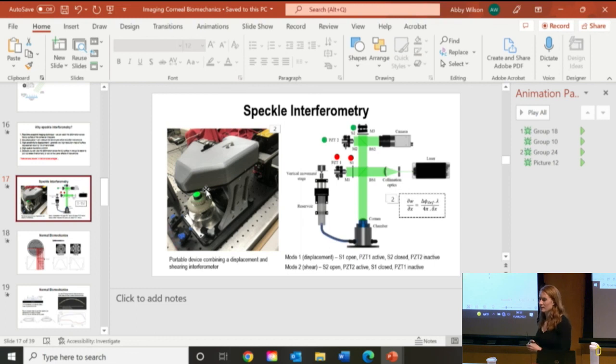On that particular slide, I'm curious, how did you get the cornea itself secured in the special chamber you're using there? Okay, so those chambers you can actually buy as a commercial anterior chamber, and they're used for the preparation of donor tissue before it's transplanted into an eye. There's a water chamber underneath. Under the cornea there's basically a snout where water will come out, and over that we 3D printed a cap with the right aperture for the chamber. We just push that cap on, and you can see that collar there. That's a threaded collar, and that exerts a force onto the cap, so it pushes it and holds the cornea in place.